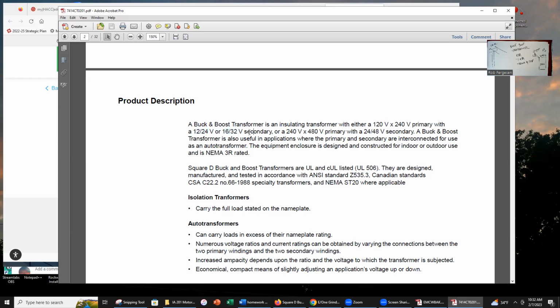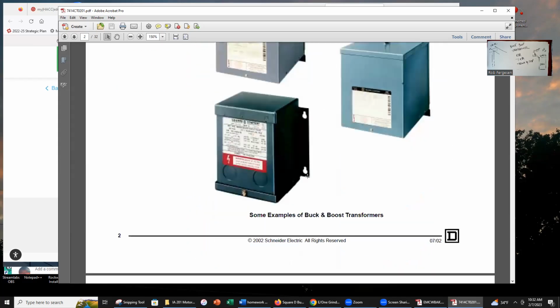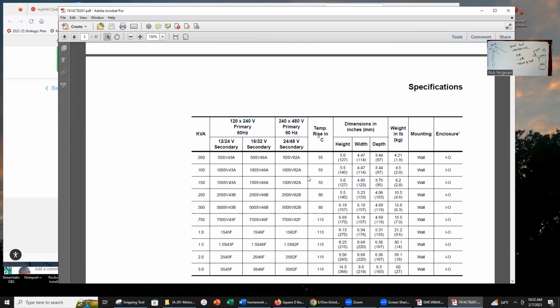And that 32 volt secondary is what I want here. I want to be able to drop my voltage by 32 volts. I also have the option of 240, 480 or 24, 48 secondary. I don't want that. I want this one right here. So let's go pick the right transformer for that application.